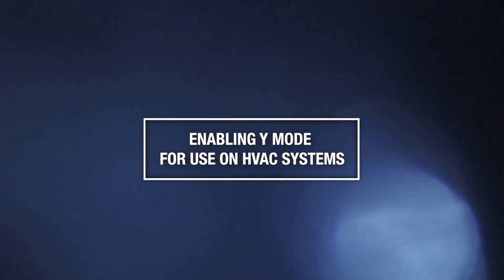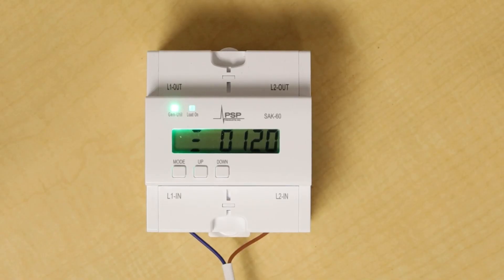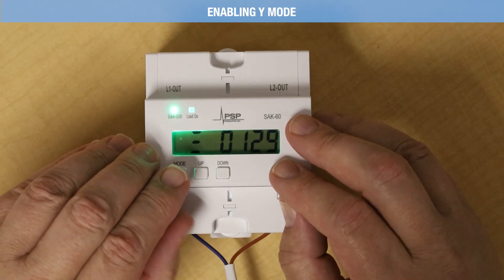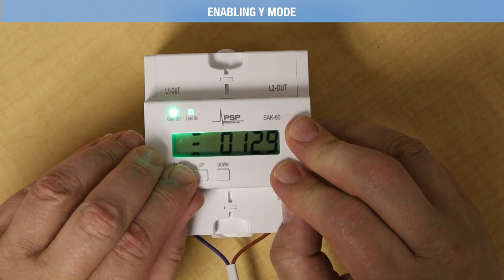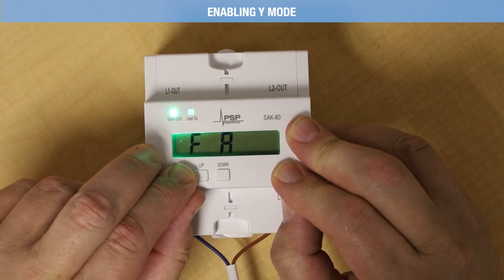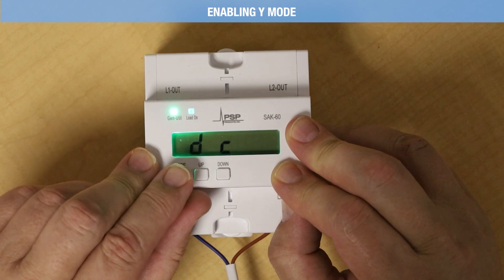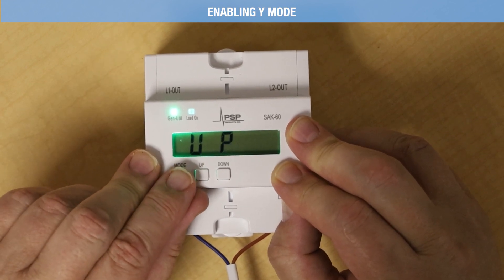When using the SAK60 on an HVAC circuit, you should enable Y mode. Y mode is only used on HVAC systems and will prevent extended reverse cycling of scroll compressors upon return to utility power. To enable Y mode, first hold the mode button for about 3 seconds until 2 digits display. Press the mode button to scroll to UP.